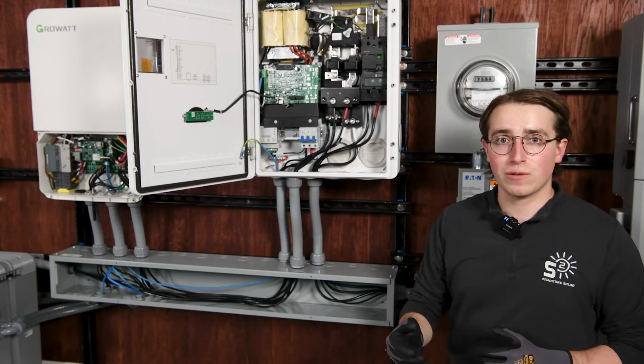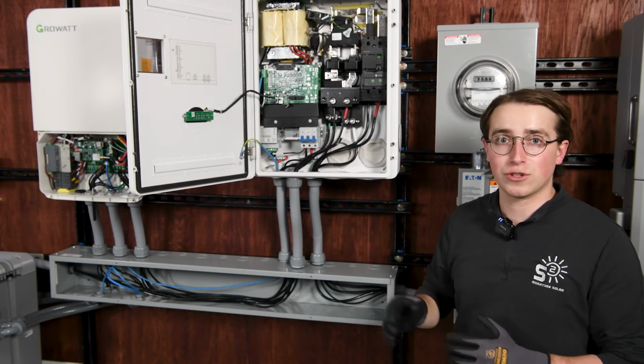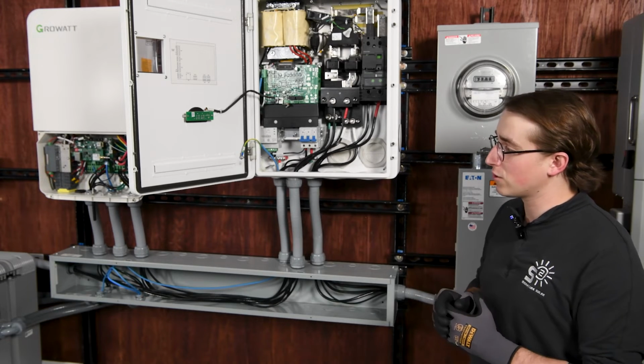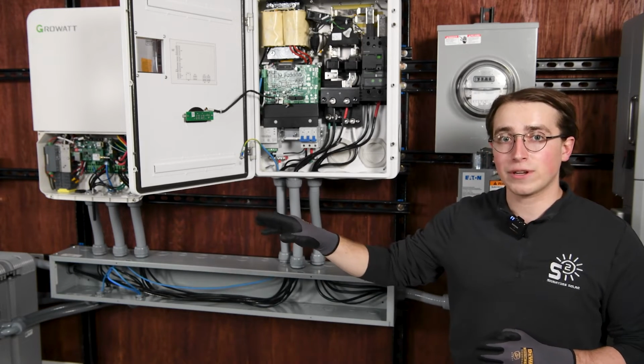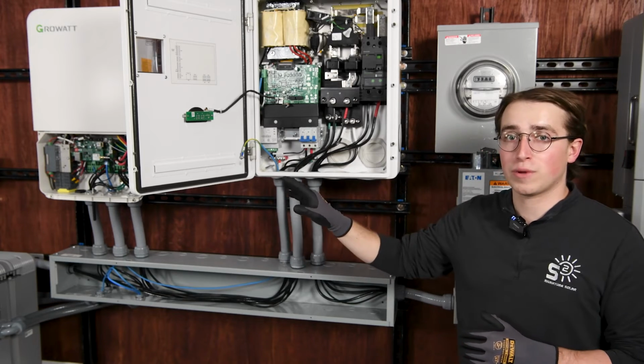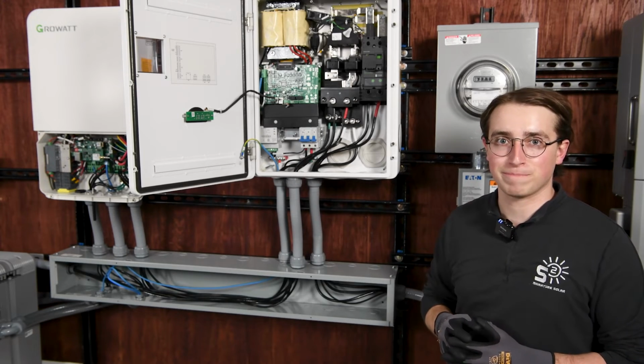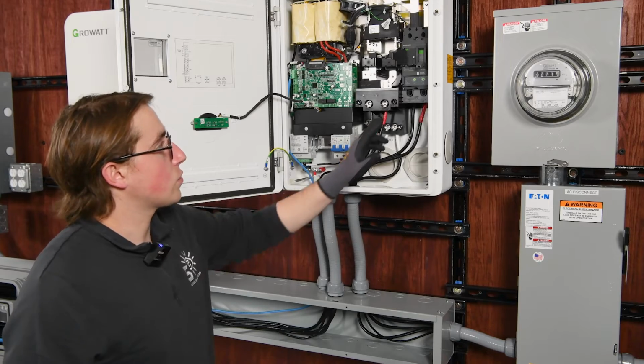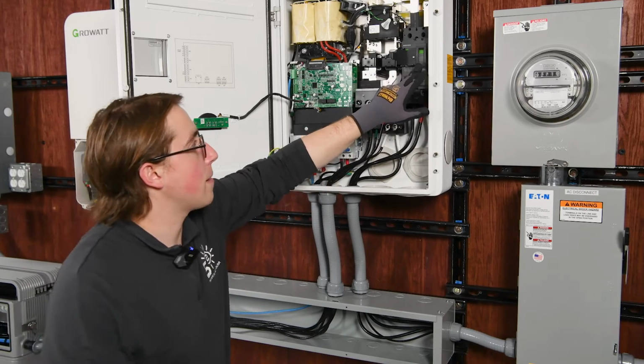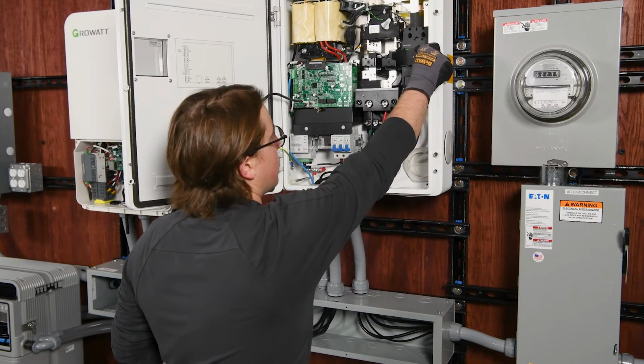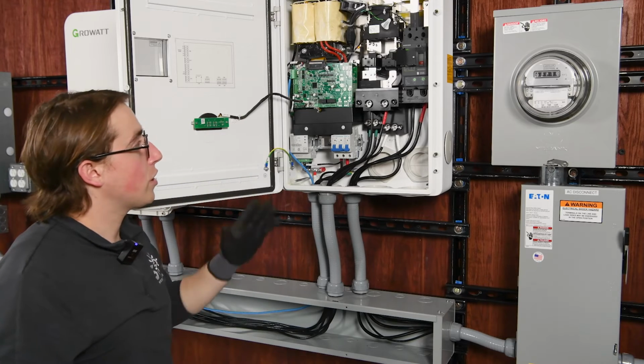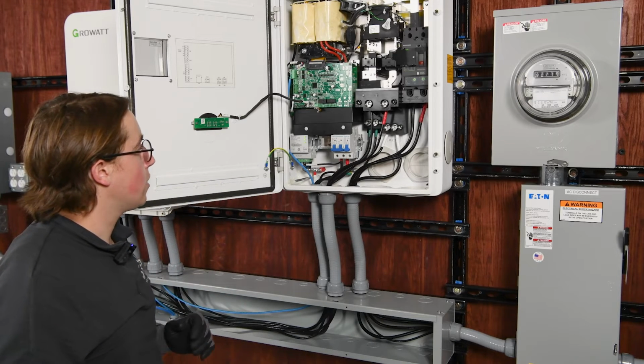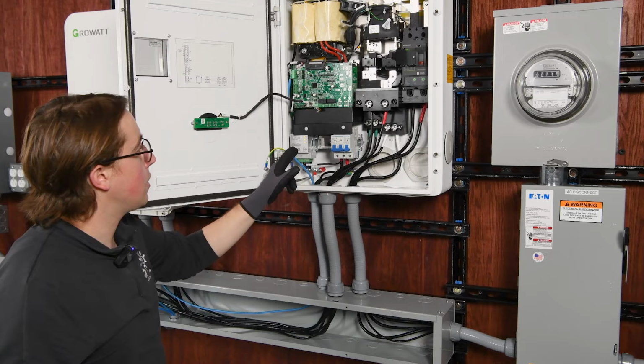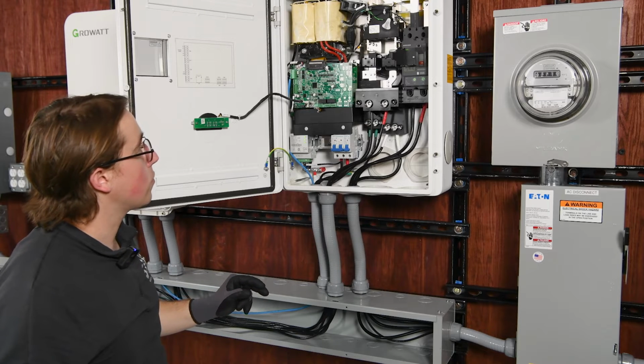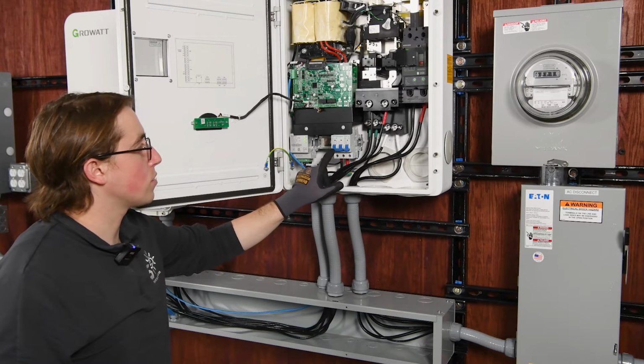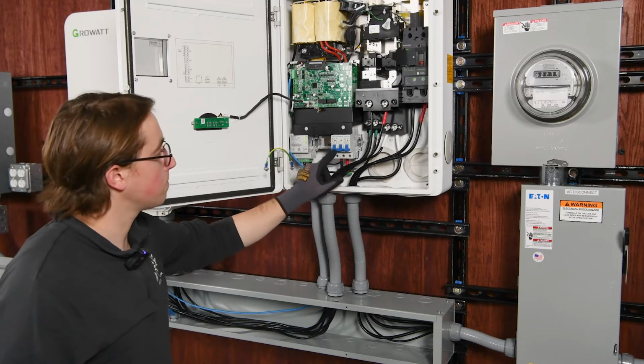With all of our cables run, we'll next perform a continuity check to ensure there's no cross polarity between our conductors. After that, we'll power on the batteries and then the grid to ensure there's plenty of power to commission the rest of the system. With grid power now supplied to the SYN, we will turn on the 200 amp main breaker here. Not sure if you can hear it, but there are relays that clicked on. Our electricity meter is now indicating that there's power. And this breaker right here will supply grid power to our inverter.